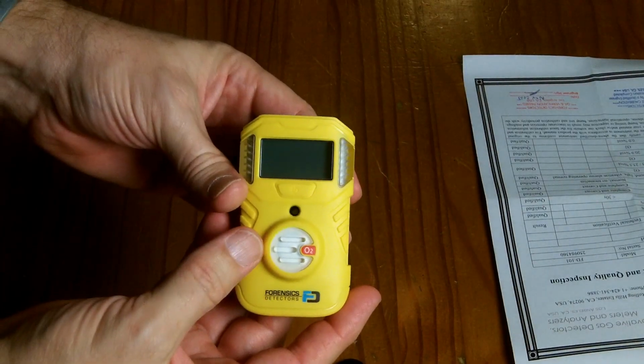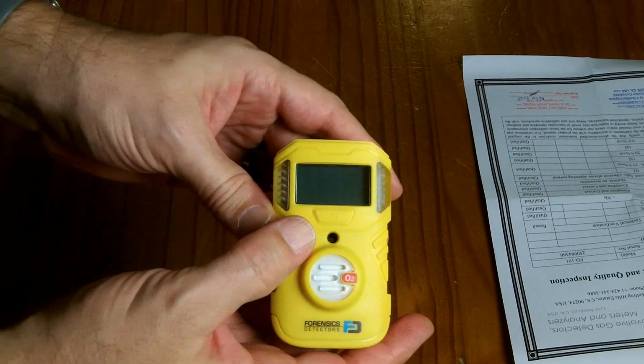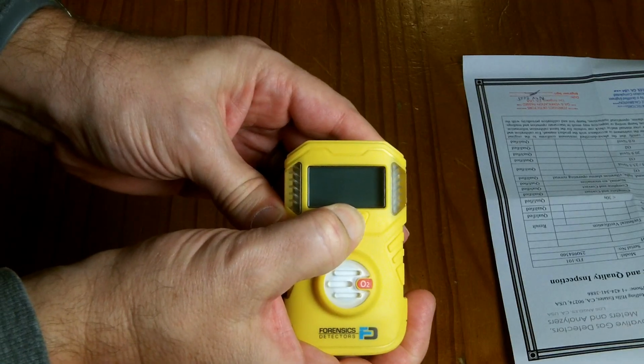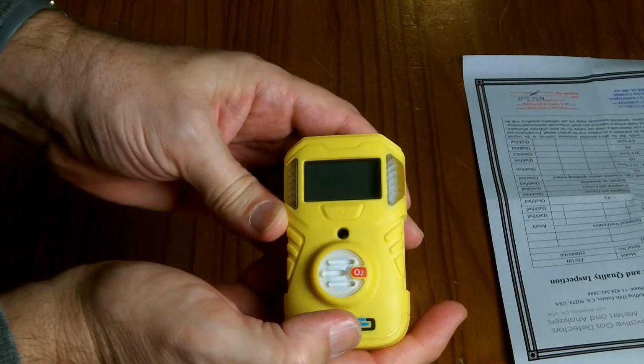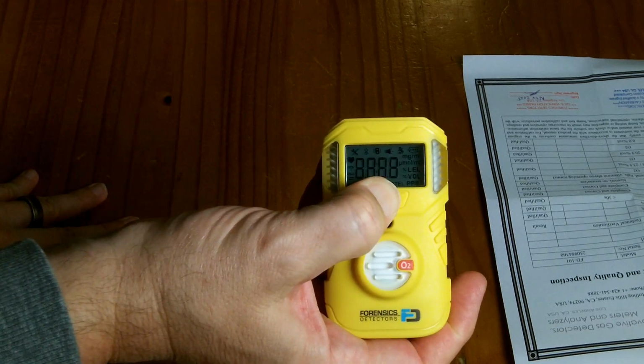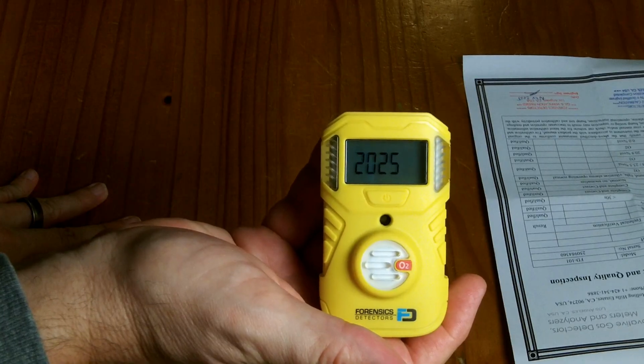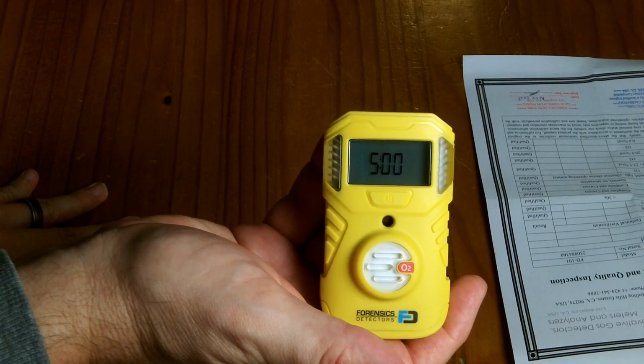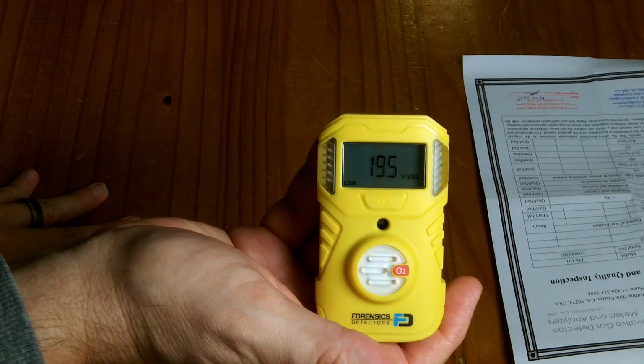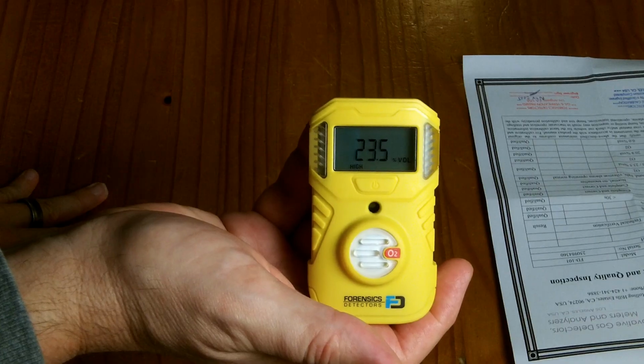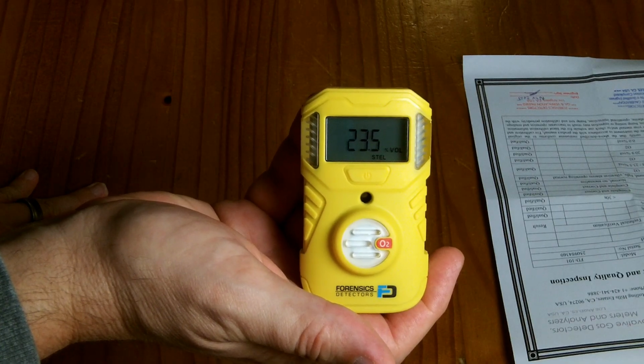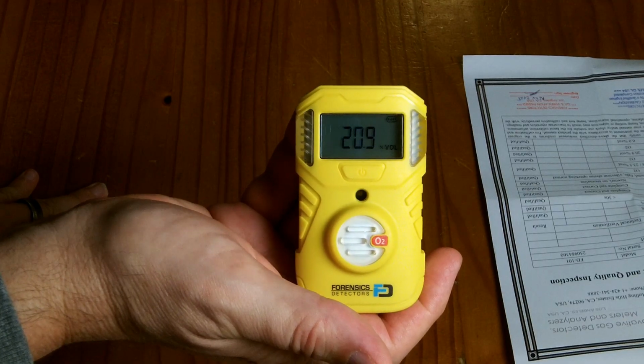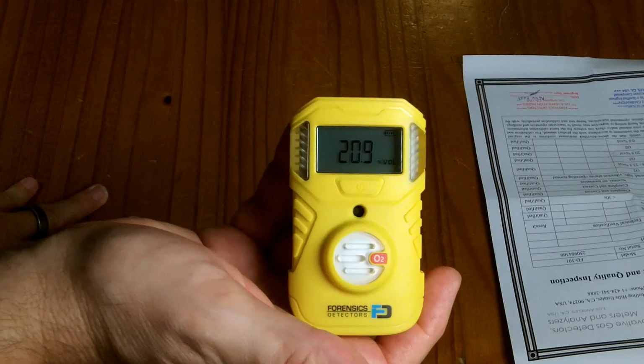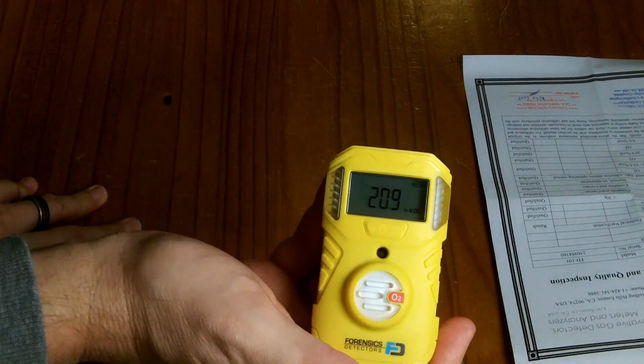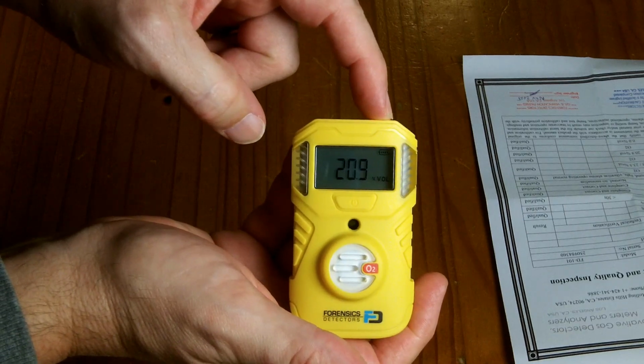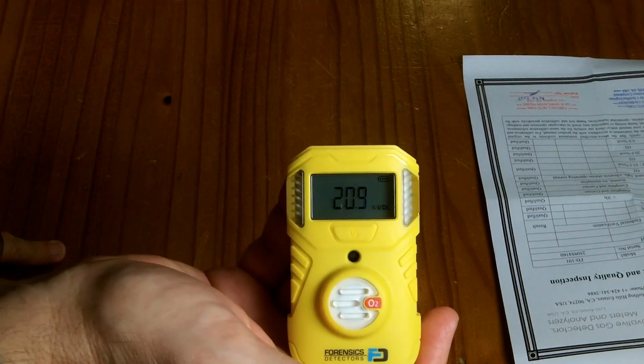Alright, so they say it comes pre-calibrated at the factory. When you first turn it on, it's supposed to go through kind of a self-test setup. So we're going to hit the button here. Alright, we're going to push and hold the button for a while. There it goes. Alright, it says it's 2025, 1202, 500. And 30% by volume, just jumped down to 19.5, 23.5 for the high and the low, time weighted average, short-term exposure limit. Okay, I believe it is now done with its little self-test startup, and it says currently we have 20.9% by volume oxygen, which is good because that's what I was expecting it to be.